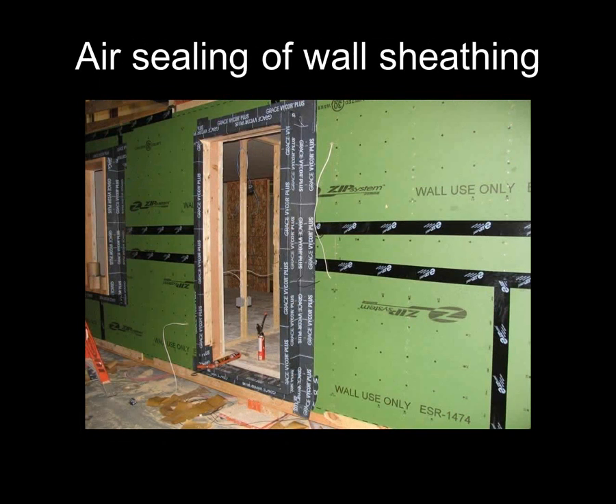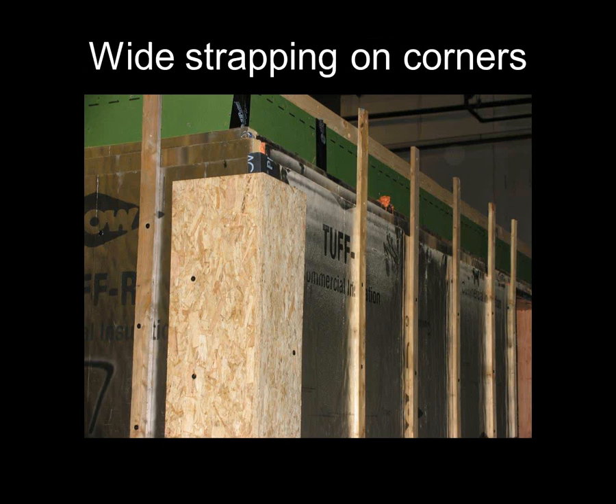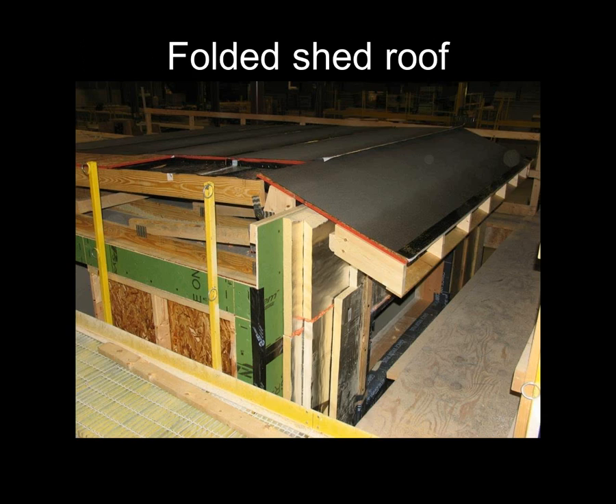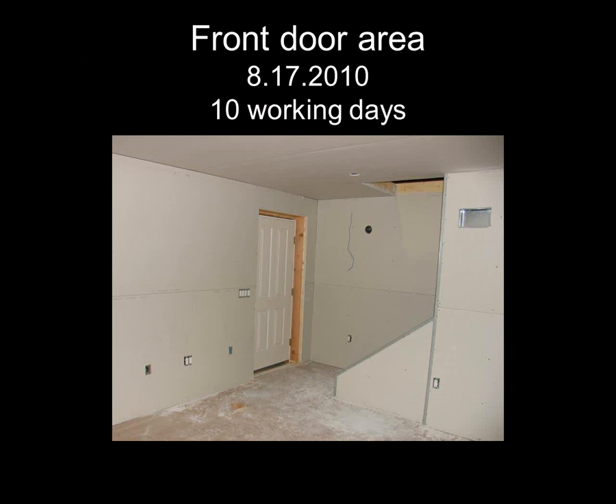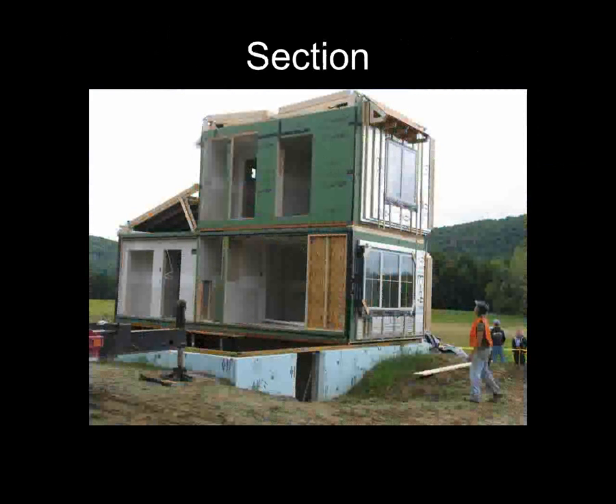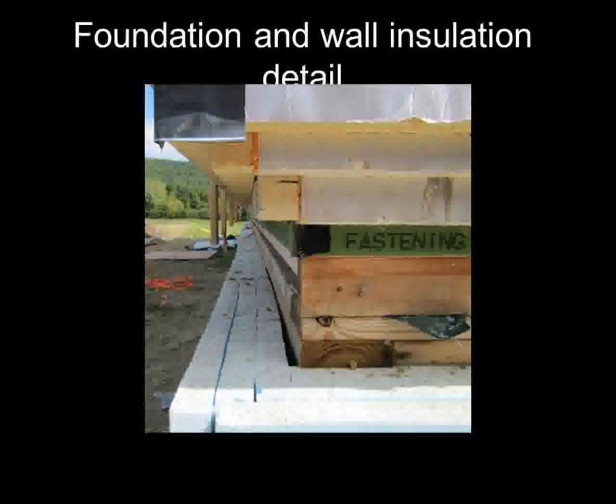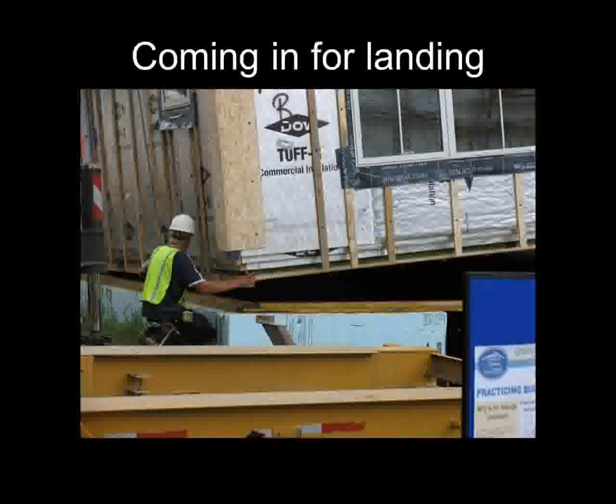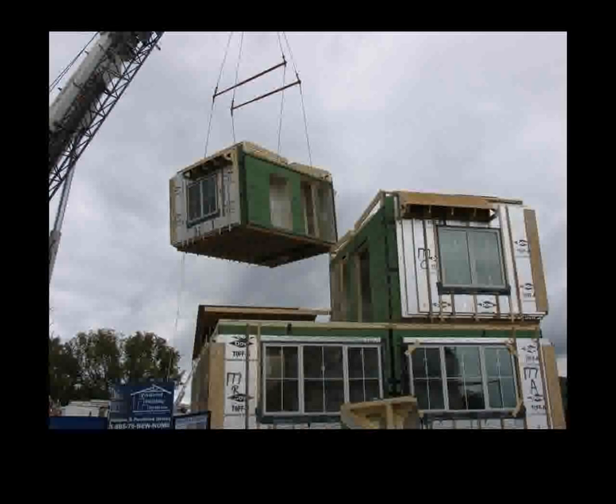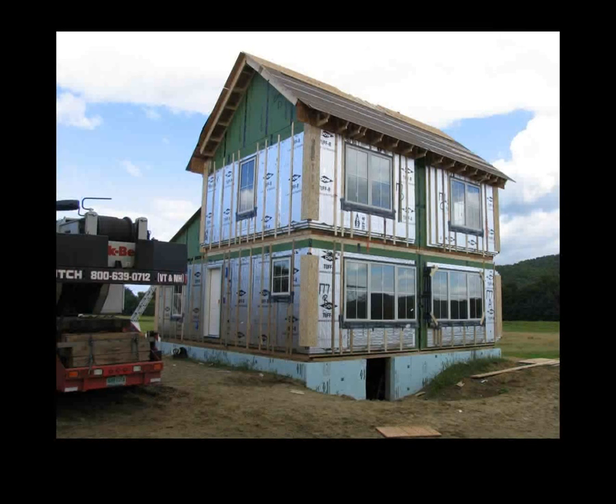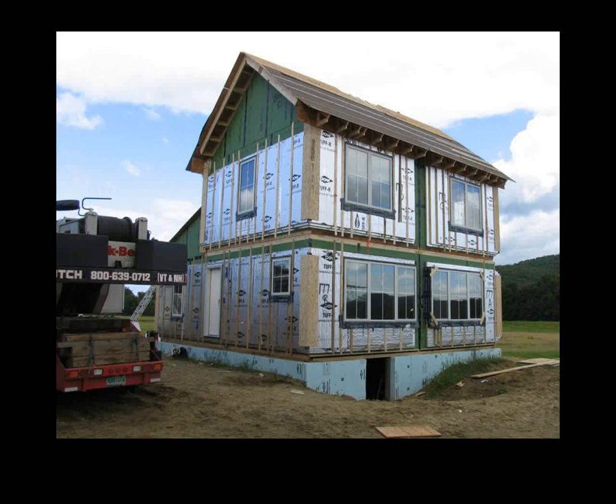Now you can see the ZIP wall, which was taped, and all the window and door installations air sealed. Here we have the rigid insulation being screwed and strapped to the exterior of the building. And that was done in 10 working days. So modular, although not critical for passive house, worked well for this particular project. And here we are assembling that building that morning in September of last year. So what was critical after the building was assembled, was that the Habitat volunteers would go in, seal up all those seams, and pull the rigid insulation across to complete the thermal bridge-free envelope.